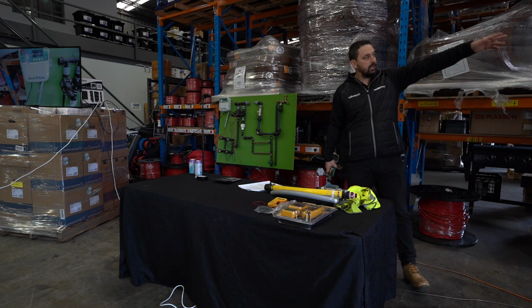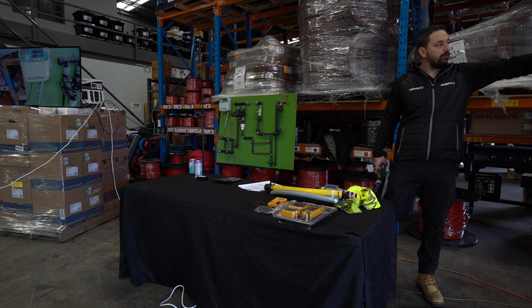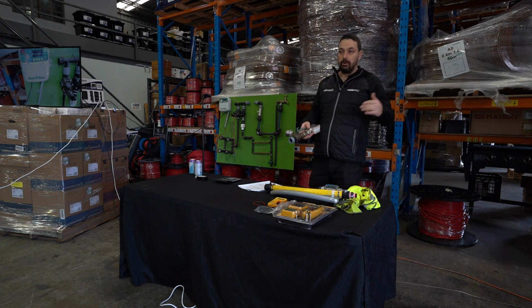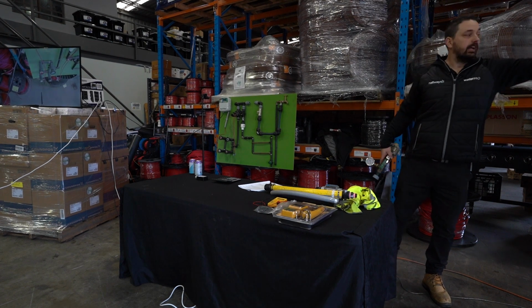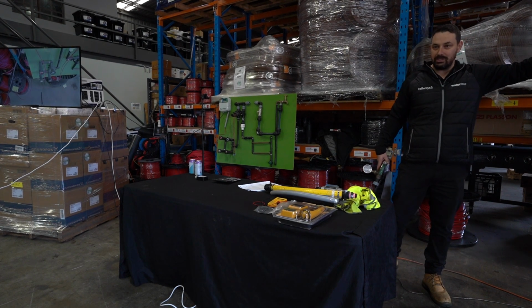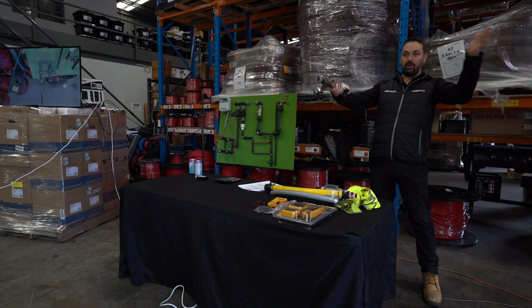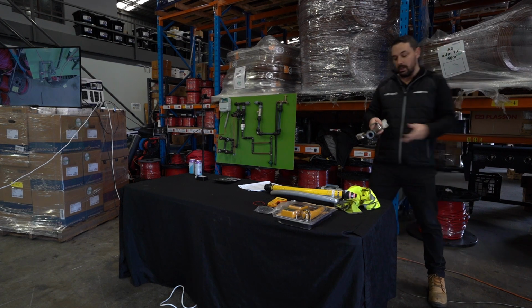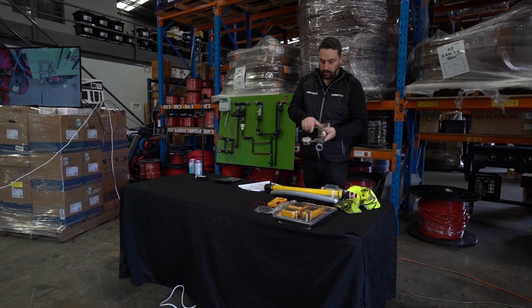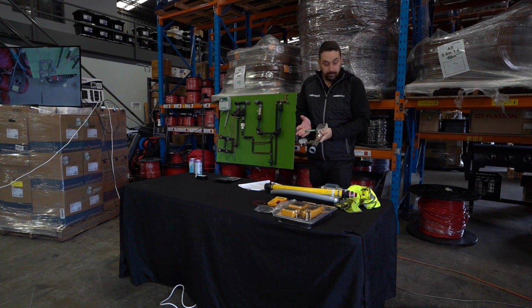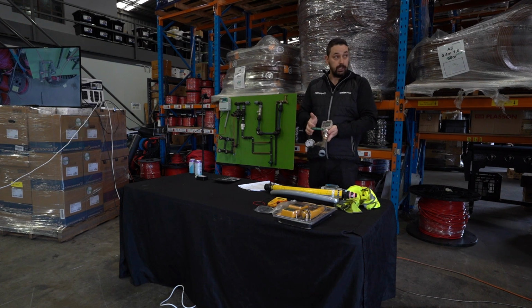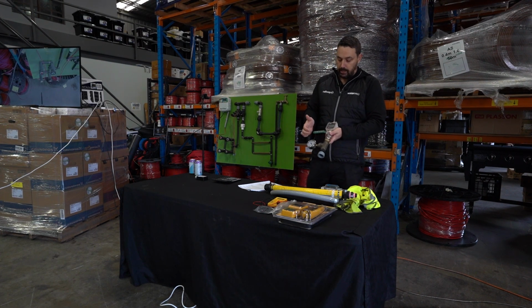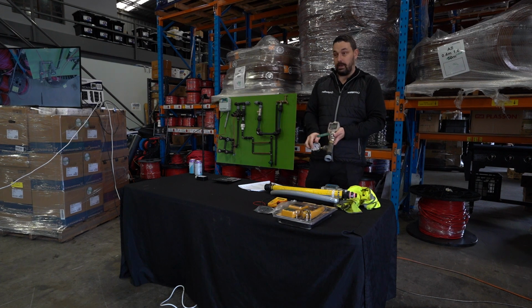And what Clint's done here is fine. We've got a 300, 400 and a 500 kPa pressure rating. Now if the pressure was only 300 here, I'm obviously not going to get a 500. I would say I want 3 points in between 0 and this highest number. So what we would do here is crack this open from being closed, which is our static, and we would then start to see that come down from the 650 kPa pressure, and we would open that up until we saw 500 kPa on the dial.